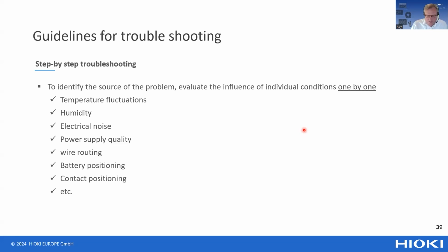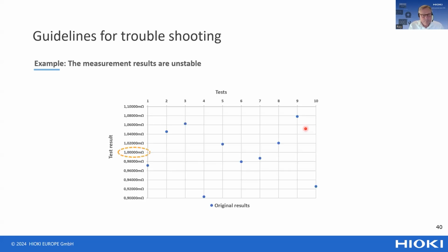We have made an example, which I'll share on the next slide. In this example, we're measuring a battery with an internal resistance of 1 milliohm, but the repeatability of the measurement is quite poor, as you can see. So something is wrong, but what is the reason? Why isn't the measurement giving good results?